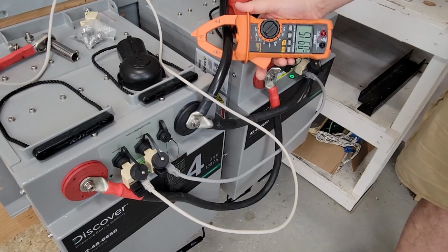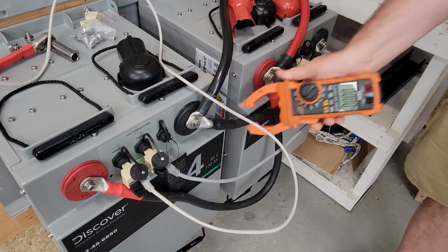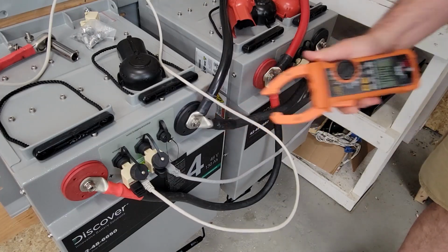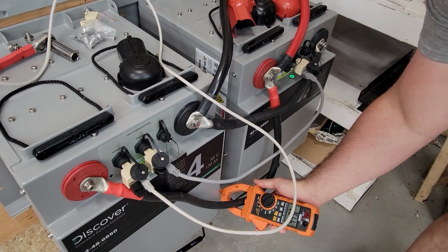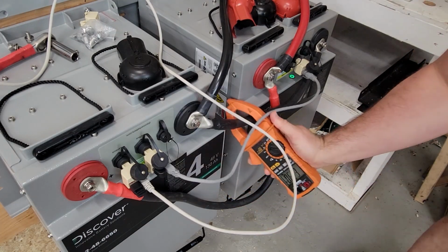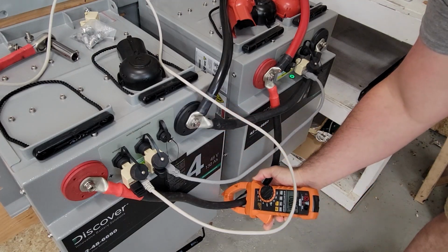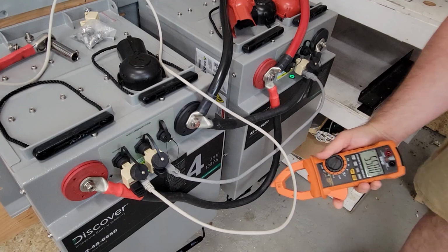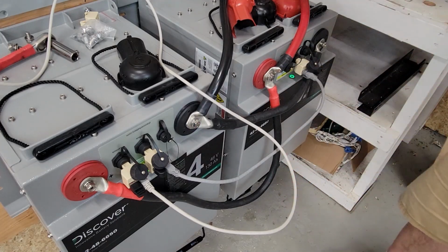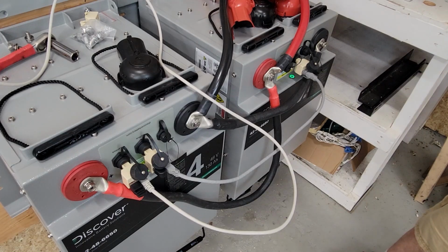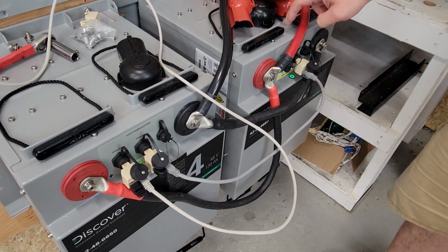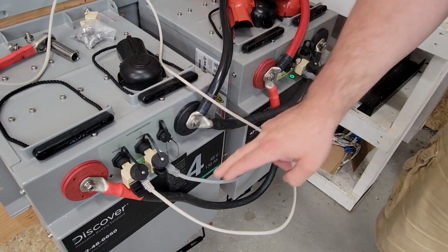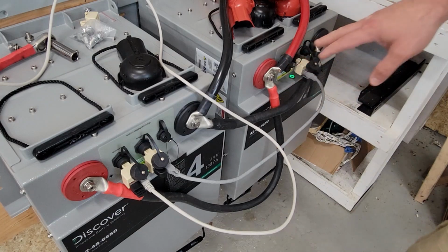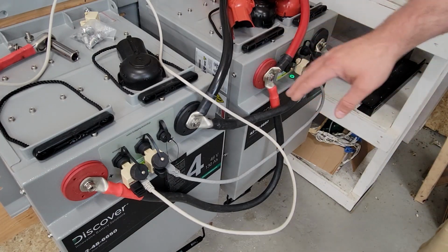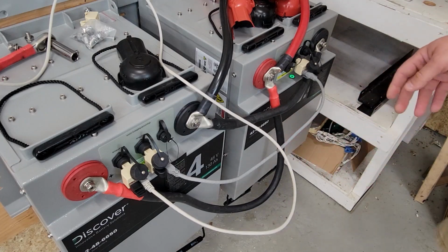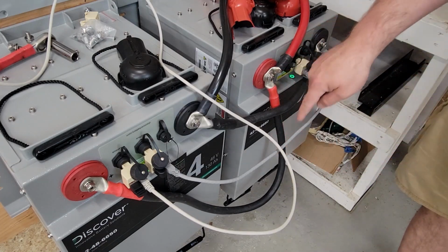Once again, up here we have 91.5 amps, and over here we have 48 amps, and over here 44.92... 48... 45. So about a 3 amp difference between the 2 wires. One battery is going to be getting 3 amps more than the next, and that's most likely this one here, because this one has a little extra resistance on this wire. They'll equal out once I take away the load, but this is amazing really when you consider how thick the 4-aught wire is and how minimal the difference is.